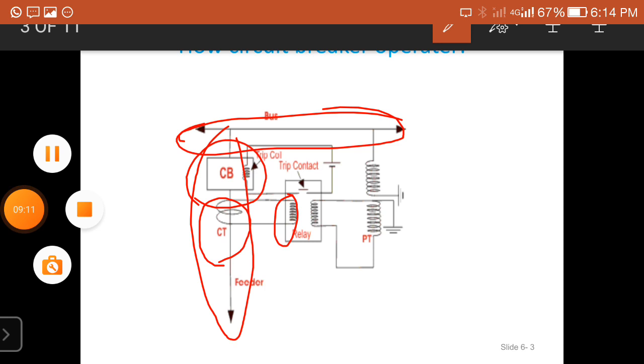An arc is produced during the separation of contacts at overloads as well as short circuit conditions. This arc is moved into the arc splitters. Then the arc is broken into particular arcs in the arc chutes, and they no longer exist due to the voltage drop of this arc. That means by using the arc splitters, we will split the arc. Then automatically the arc will be reduced.